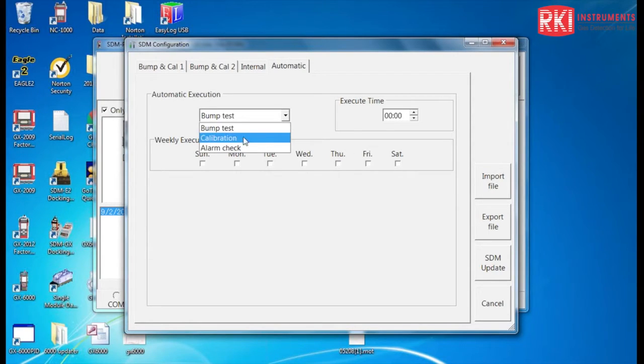A bump or a calibration or an alarm check at a particular time of day and a particular day of the week. And we've had people ask for that where they say, we want our guys to put the instruments in the dock every Friday, and then we want to make sure that they're all calibrated on Monday morning when they pick them up without them having to do anything. So that's what you can use this function for.